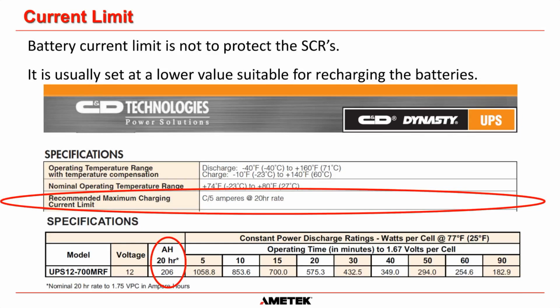Another question, can we install for a temporary time batteries in parallel with the same voltage but different ampere hour? Absolutely, yes, you can. But obviously, if you temporarily put a battery in parallel that has less of an ampere hour capacity, those batteries are going to get to their end of discharge quicker, and then you will be back to just having one battery, if you know what I mean. But yes, you can do it. It's not recommended, but you absolutely can do it without any issues.